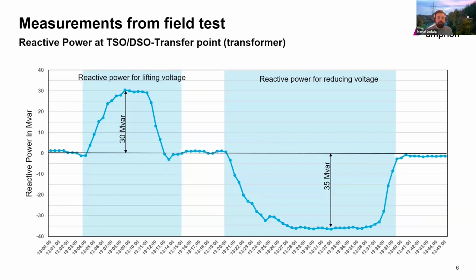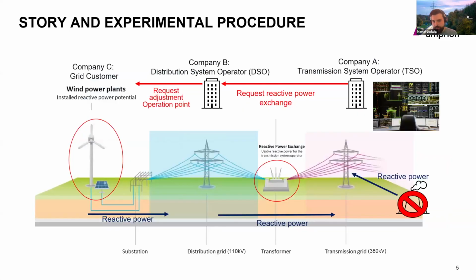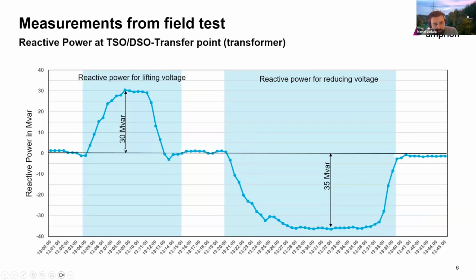Here you can see the field test measurement. I will show you the reactive power control at the transformer. Let's look back: here you can see the transformer between the distribution system grid and also the transmission grid, and this is a measurement at the transformer.